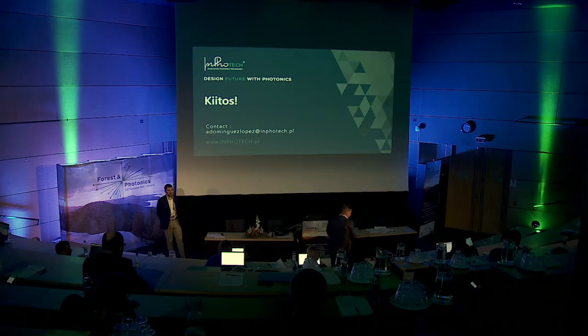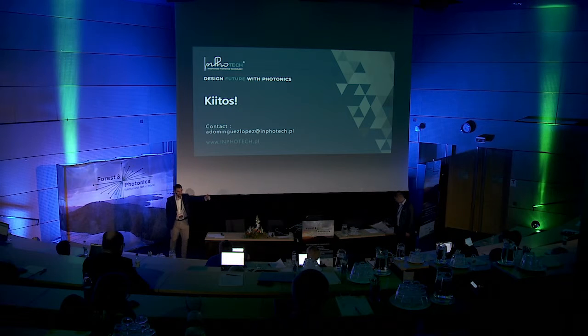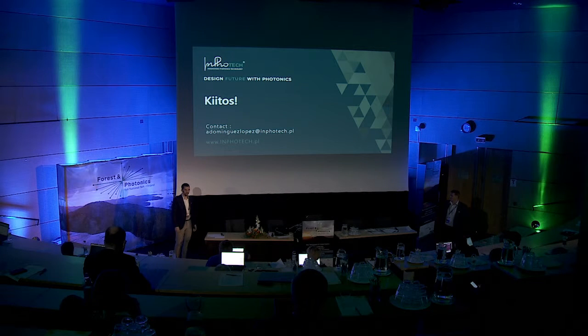Thank you. So just to clarify, what is the distance you can measure in the fiber, for example, for temperature? How long can you reach in the fiber? So 50 kilometers is the standard distance, and at 50 kilometers you can have information every 2 meters of the fiber. Right? The maximum range, the state of the art, is a bit higher, but for commercial applications, it's around 50 with 2 meters plus resolution. Okay, thank you.